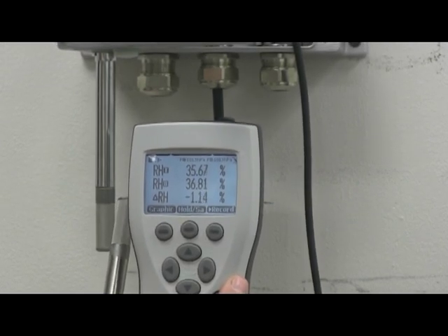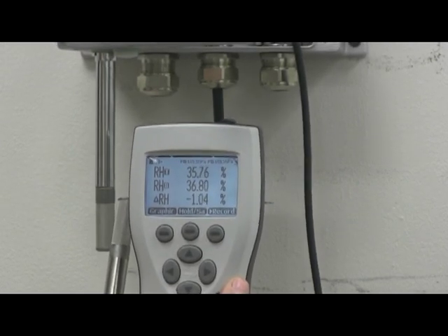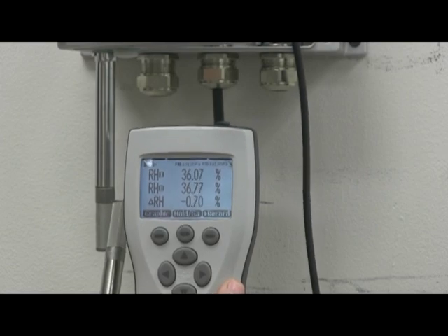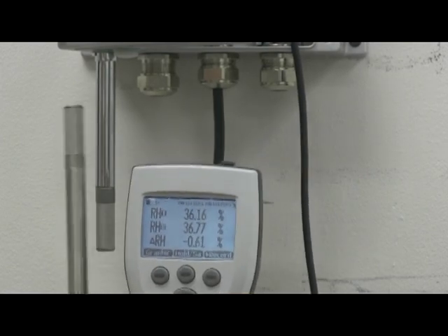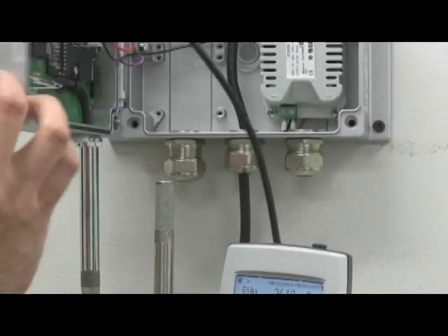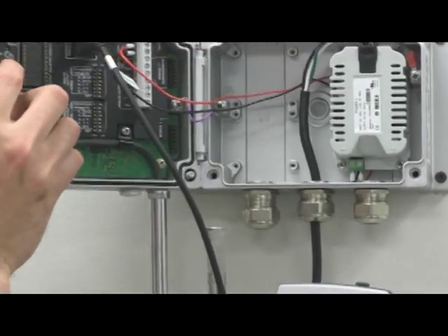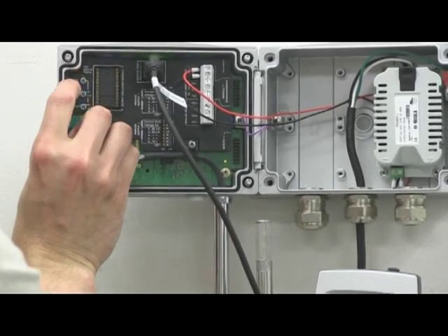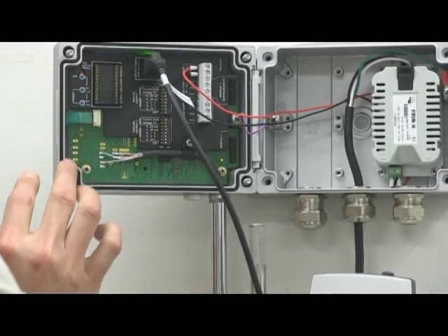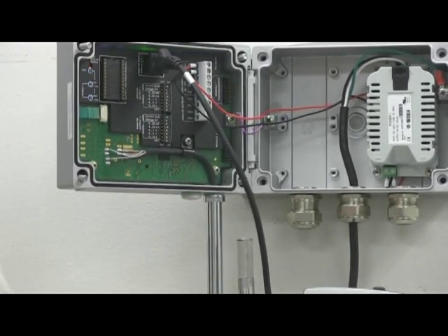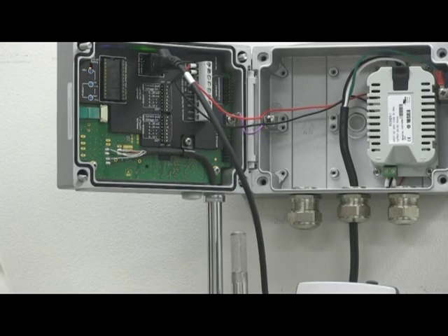Step 3. Press the adjust button on the motherboard of the HMT331 and the LED light will begin flashing. From here, we'll simply follow the prompts on the display of the handheld to complete the calibration.